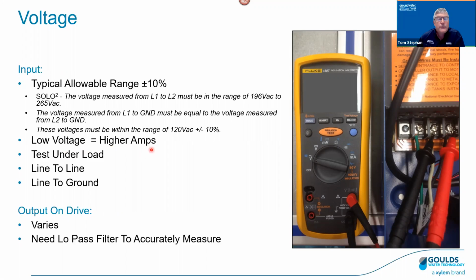So, low voltage. The reason why we're checking that, obviously, is: do we have voltage? Do we have the proper voltage? Is it high? Is it low? Because low voltage and high voltage can lead to high amps, right? So if we're getting high amps, maybe it's tripping or something like that, we should go check the voltage. If possible, test under a load. Now, if the pump is not running, this is not possible. That just means that the pump is running.